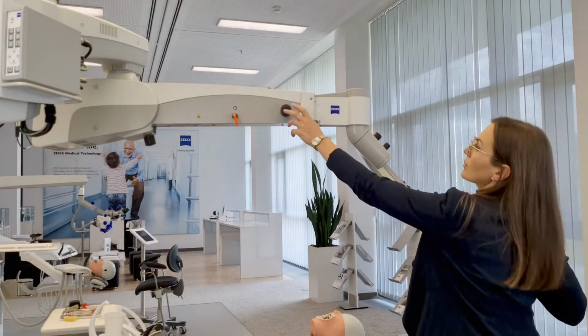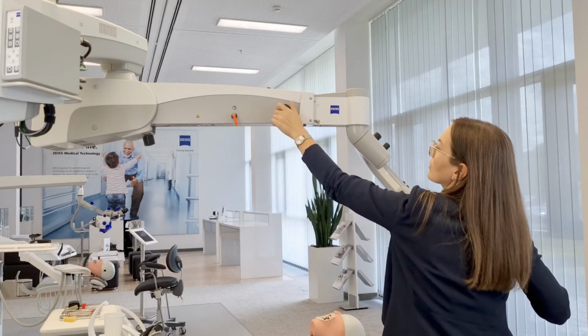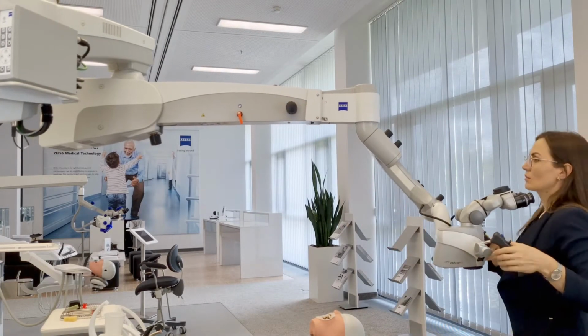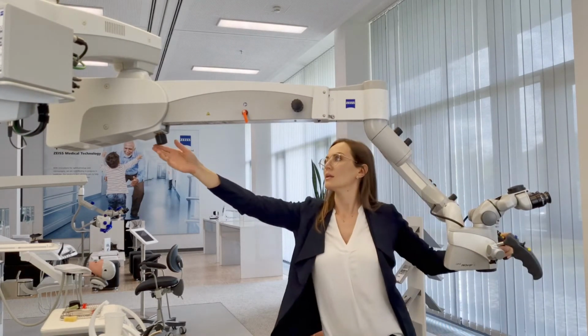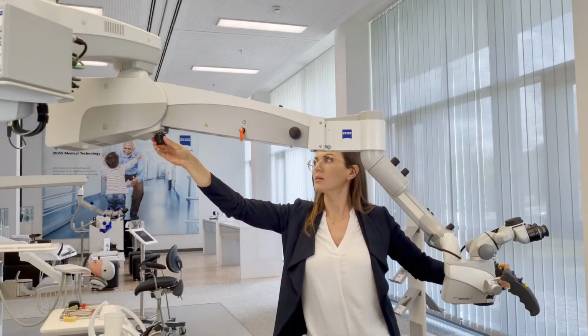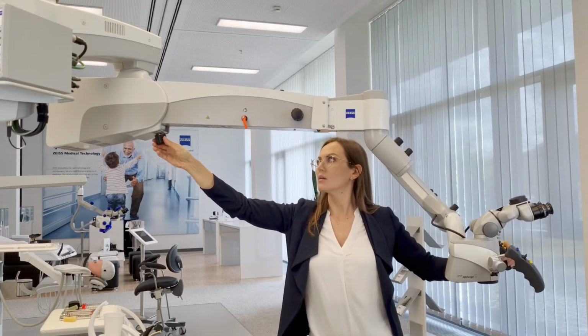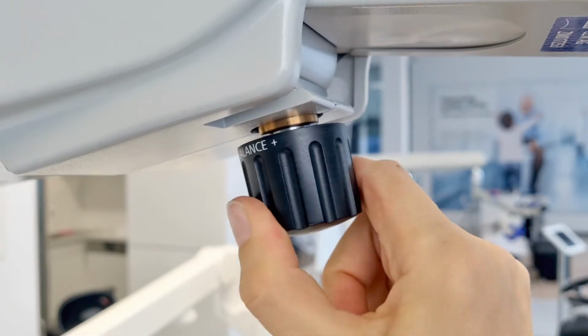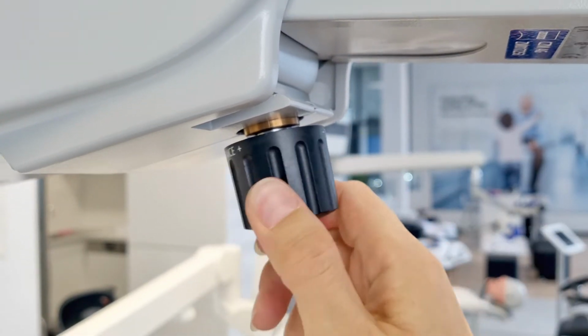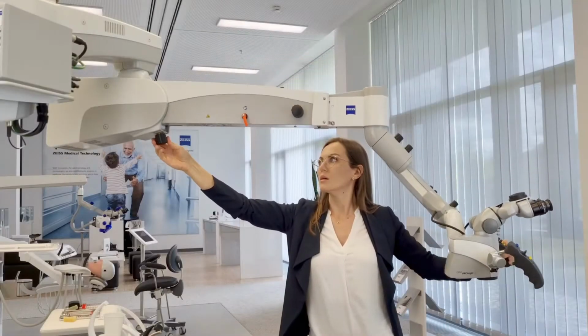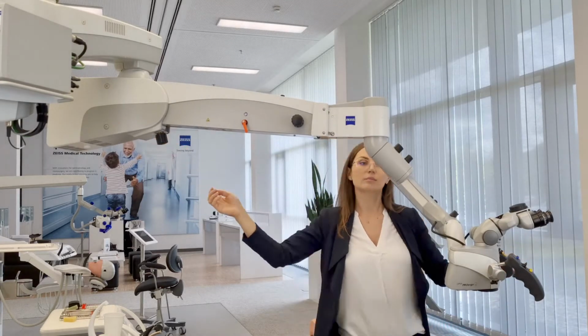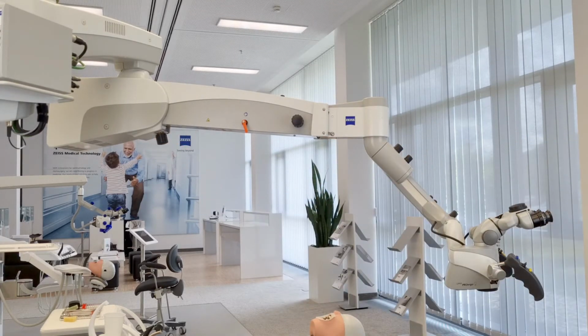Hold the microscope tightly by its hand grips and loosen all friction knobs on the suspension arm. Turn the balancing knob to either plus or minus to compensate the added or removed weight. Turn to plus if you added weight. Turn to minus if you removed weight. When balanced correctly, the arm should stay in place at every position.